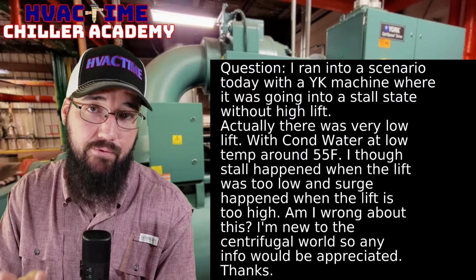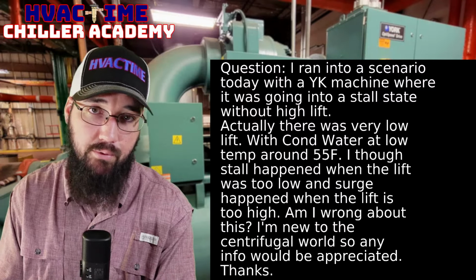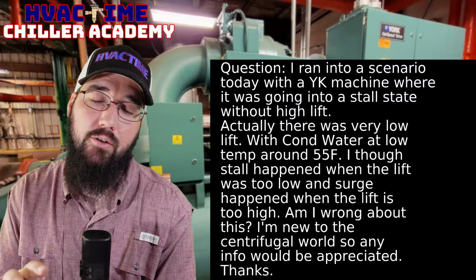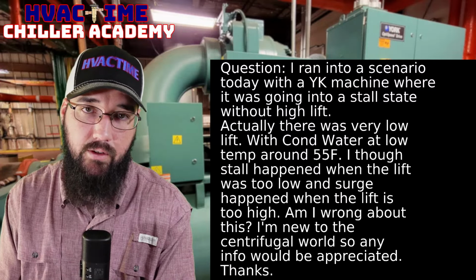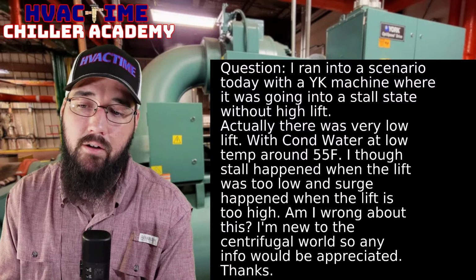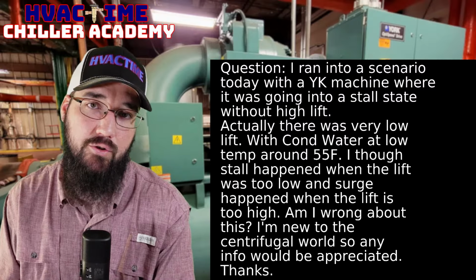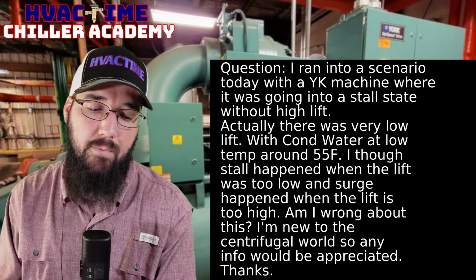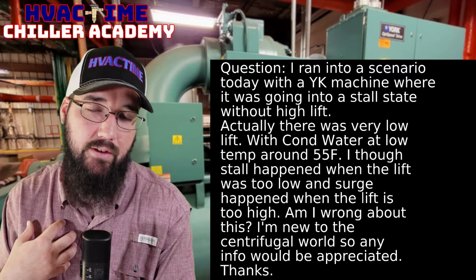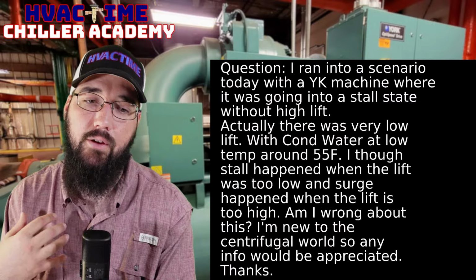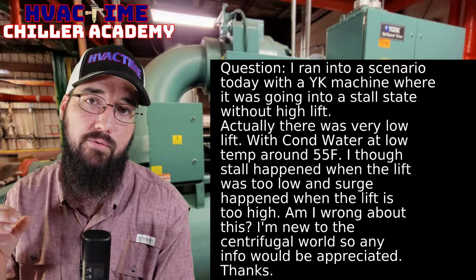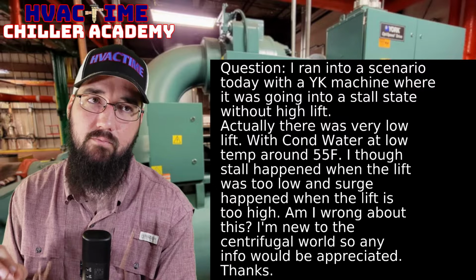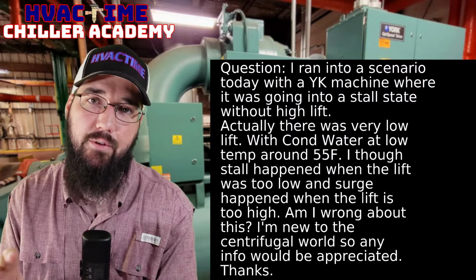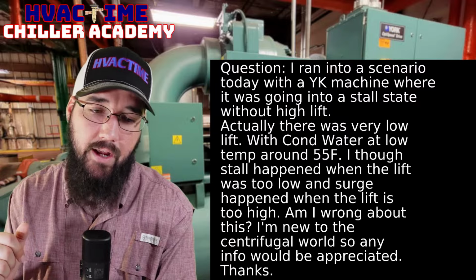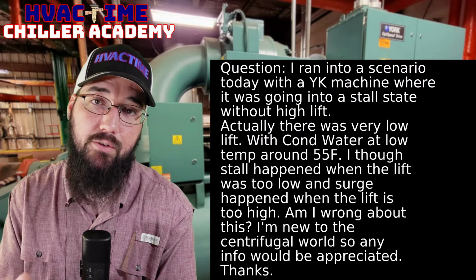And that graph changes for every compressor. Every compressor is slightly different in terms of model of compressor specifically. So every compressor model and design has a slightly different surge graph. And these are not things that we typically have access to in the field ourselves. We don't get those charts for most compressors. That's something that the factory holds internally on their side, but it is built into the control logic.